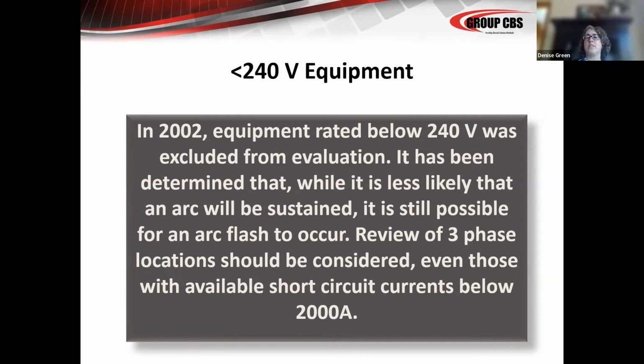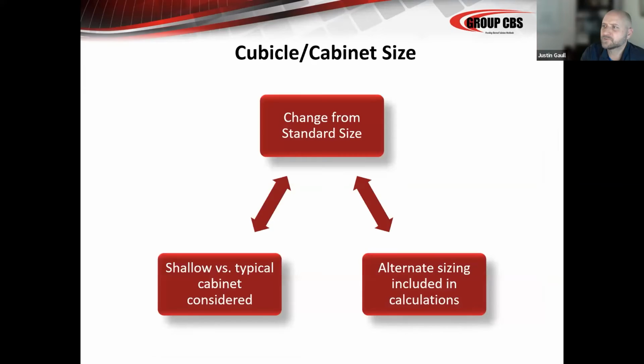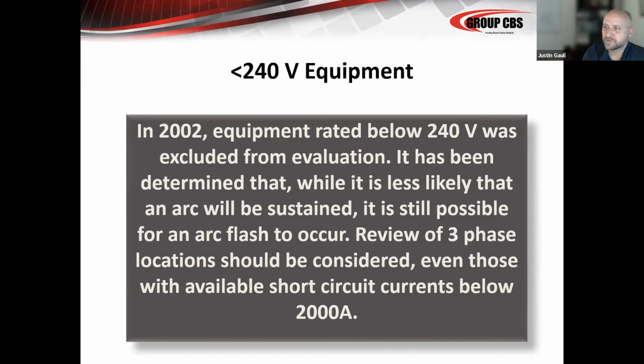But as far as evaluation, that's related to the condition of the breaker, right? Yeah. Arc flashes also happen quite frequently when we're using underrated tools or equipment, or there's human error, right. But if there's damage to insulation, if your insulation system is failing because your equipment is in a poor environment, you haven't been inspecting it, you don't know that the insulation is failing, then you can have an arc flash incident, even at 240 volts.